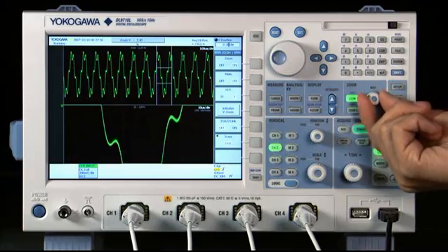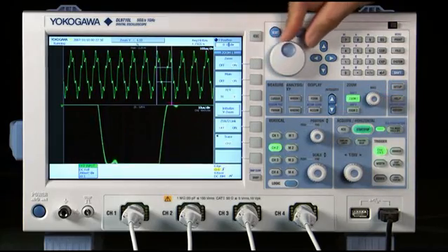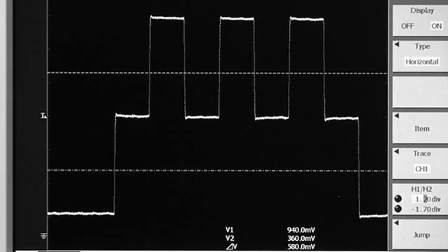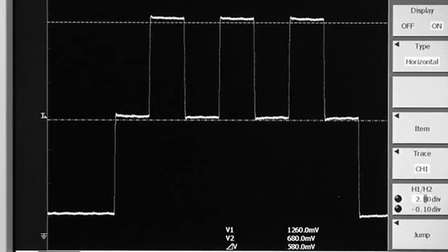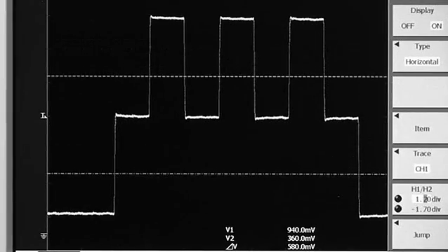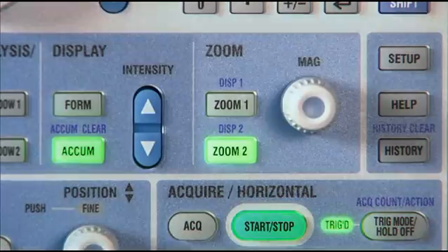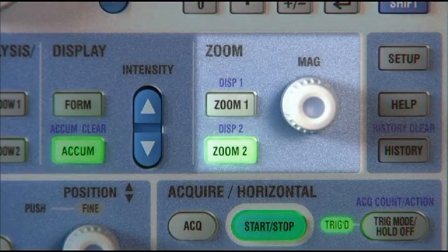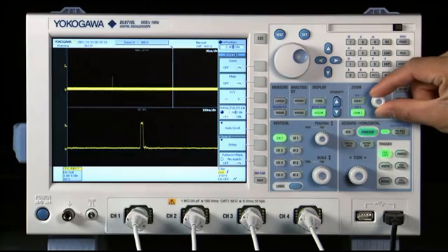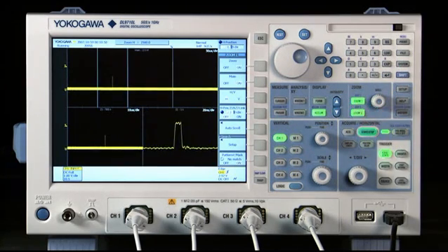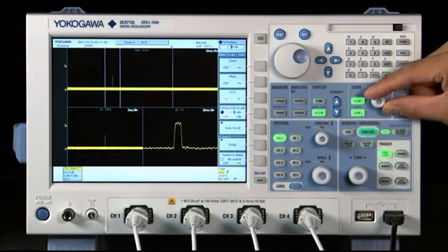All digital oscilloscopes give you the ability to make simple horizontal or vertical cursor measurements. One shortcoming of these cursors is that their accuracies are usually limited to the pixel resolution of the oscilloscope's display. The Yokogawa DL9000 avoids this problem with its two independent zoom windows. The independent magnification and position controls significantly enhance the resolution of a vertical cursor measurement.